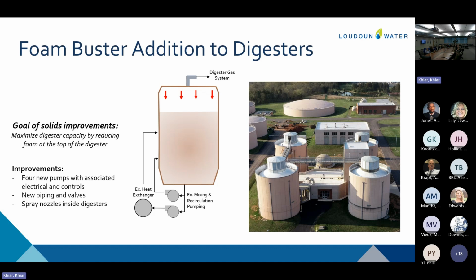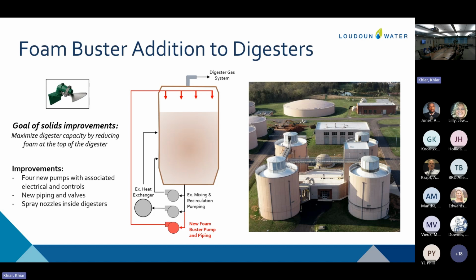We've identified the foam busters. I know it's silly, I'm sure y'all giggled when you saw that on the slides. But the foam busters work by recirculating flow from the bottom of the digester to the top, with specially designed nozzles that spray the digester contents from the bottom, recirculated to the top, to help knock down that foam. The implementation includes a new pump, one per digester, new piping to convey flow from bottom to top, and installation of the nozzles in the digesters.